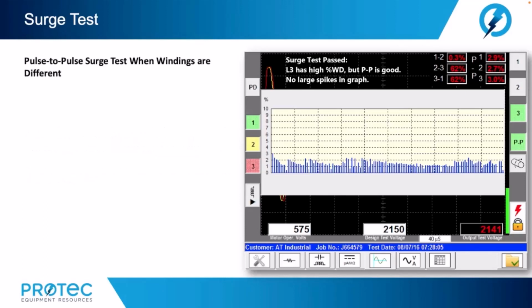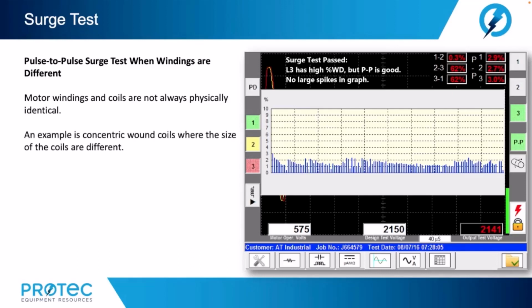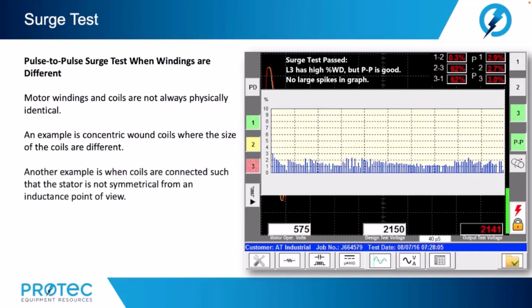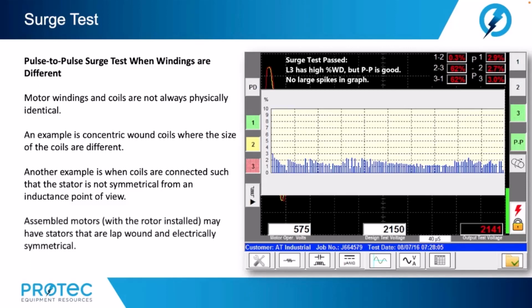Pulse-to-pulse surge tests when windings are different. Motor windings and coils are not always physically identical. An example is concentric wound coils, where the size of the coils are different. Another example is when coils are connected such that the stator is not symmetrical from an inductance point of view. Assembled motors with the rotor installed may have stators that are lap wound and electrically symmetrical.